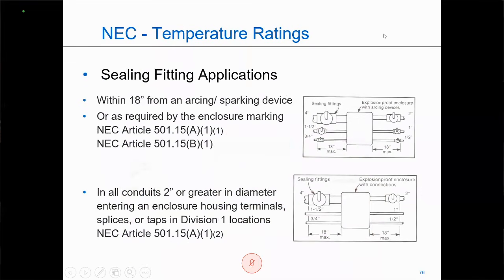You remember this slide we talked about before. Now, with this particular slide, I mentioned on the bottom, when I have a Class 1, Division 1 housing that's containing splices or taps, I need to seal conduits 2 inches or larger. The code has one other piece of verbiage that goes along with that. If the unit can heat up and exceed 80% of the auto ignition temperature of that particular gas, then all conduit need to be sealed, not just 2 inches above.